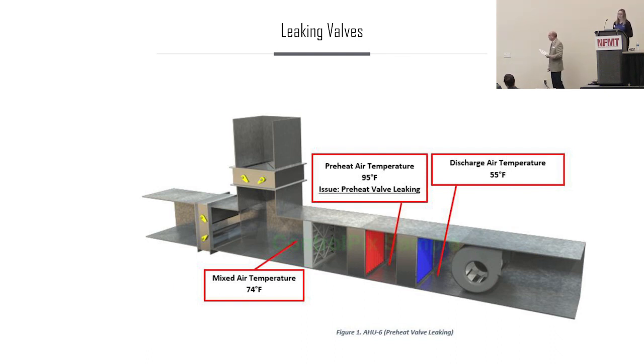A lot of buildings have leaking valves. Leaking valves are probably one of the easiest things to diagnose in a building, especially if you've got a BAS. Just run through there and command all those valves shut. If the temperature difference between the mixed air and the supply air is anything more than maybe 2 to 3 degrees, if the sensors are calibrated, then you probably have a leak somewhere, because the only heat it should be picking up is maybe a little bit off the fan. It may not be as drastic as 95 to 55 having to cool off, and I wish I had the numbers on hand, but any degree more that you have to mechanically cool or heat is money that you're spending.